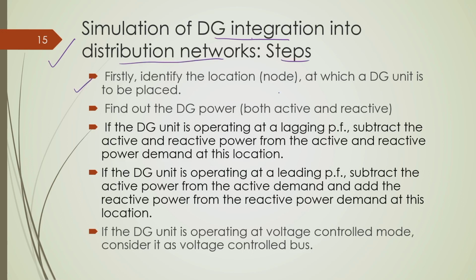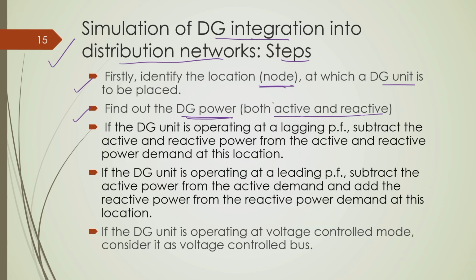Firstly, you should identify the location or node where you should put a DG unit. Then you should find out the generation of the DG, whether it is providing both active and reactive power, or only active power, and if both, how much of each. Then, if the DG unit provides both active and reactive power, it is considered to be a negative load, assuming it does not have constant voltage or regulated voltage capability.